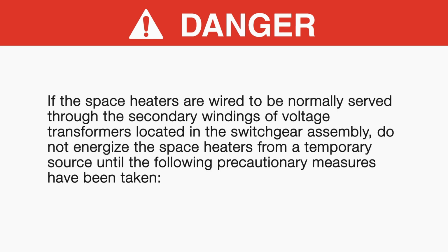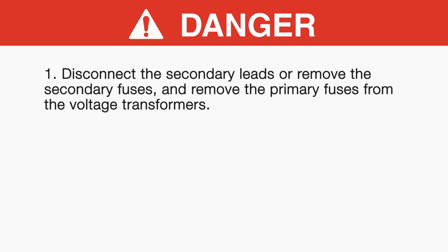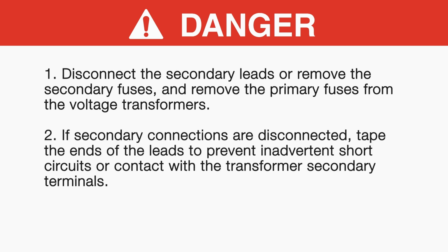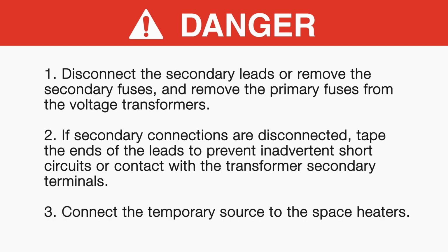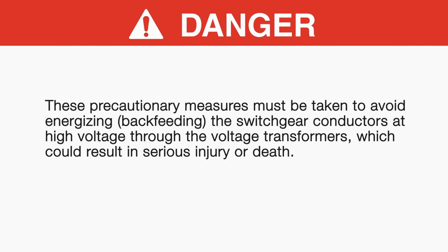Danger. If the space heaters are wired to be normally served through the secondary windings of voltage transformers located in the switchgear assembly, do not energize the space heaters from a temporary source until the following precautionary measures have been taken. 1. Disconnect the secondary leads or remove the secondary fuses and remove the primary fuses from the voltage transformers. 2. If secondary connections are disconnected, tape the ends of the leads to prevent inadvertent short circuits or contact with the transformer's secondary terminals. 3. Connect the temporary source to the space heaters. These precautionary measures must be taken to avoid energizing, backfeeding, the switchgear conductors at high voltage through the voltage transformers, which could result in serious injury or death.